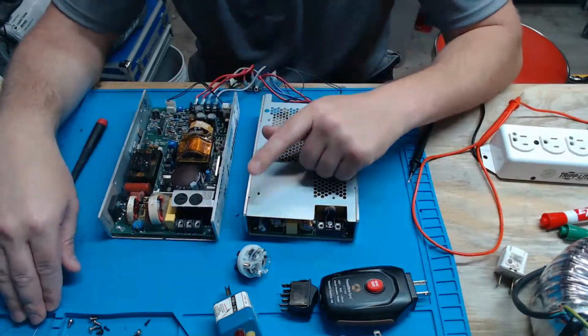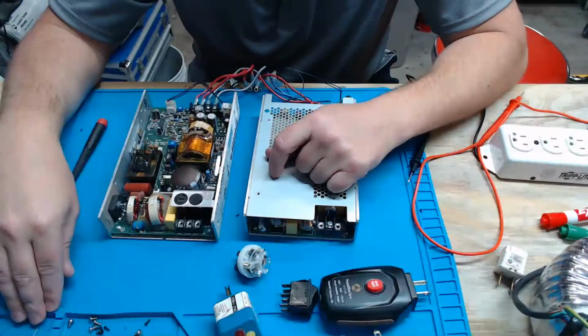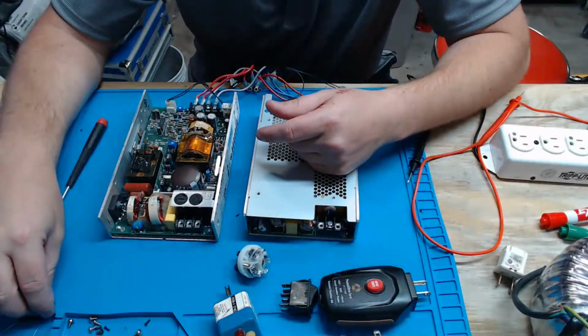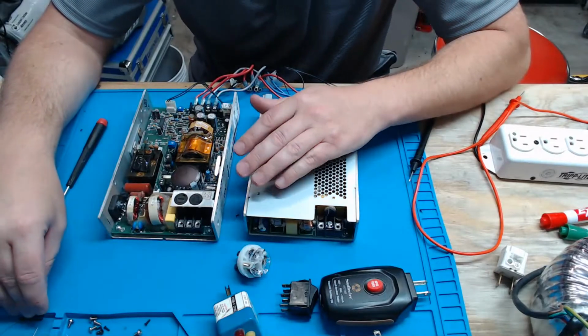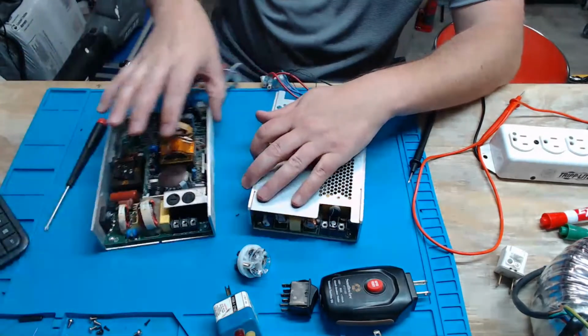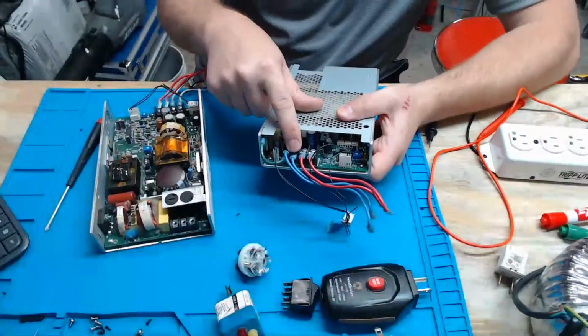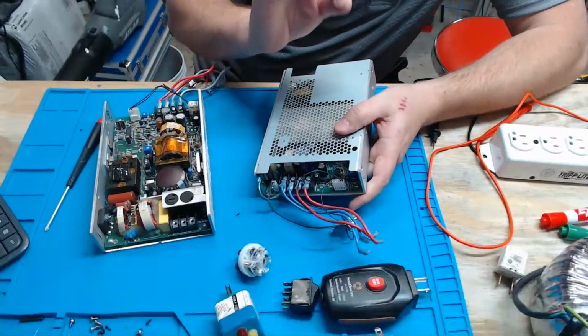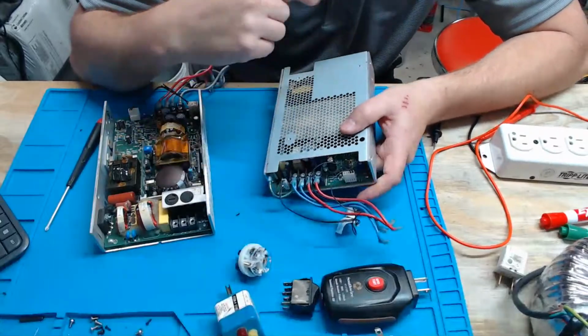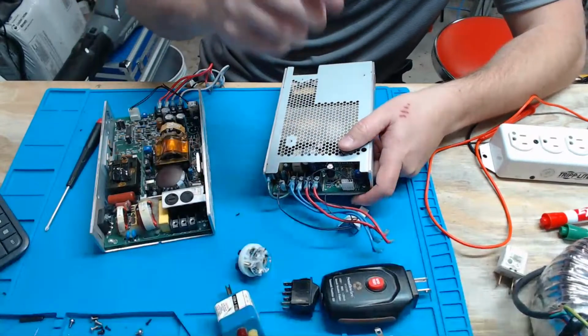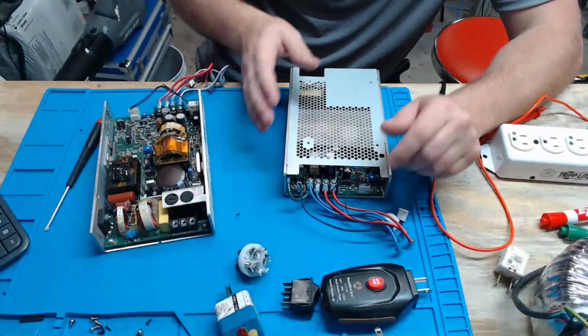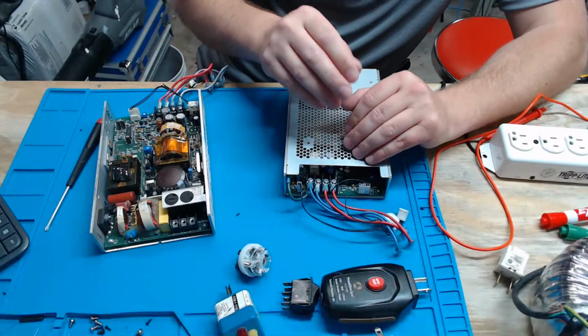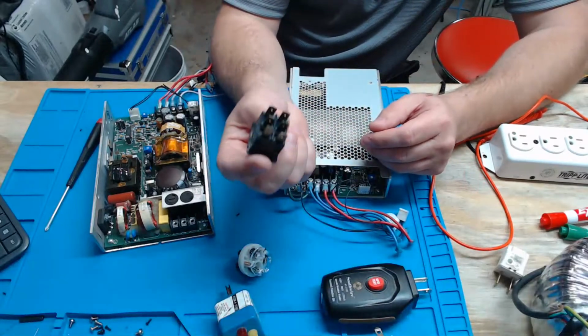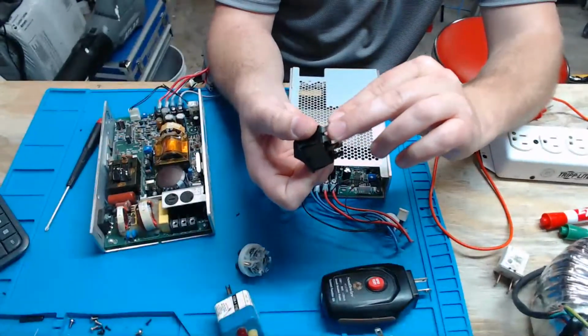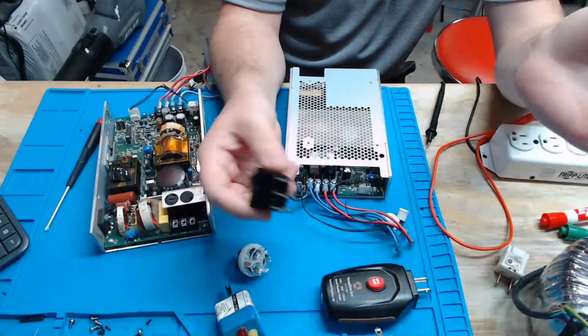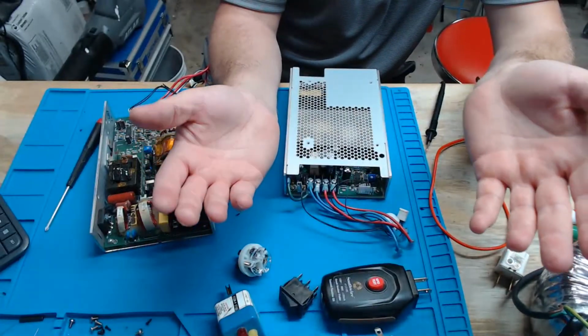And remember, guys, just because it is unplugged doesn't mean that it's safe, because most larger medical devices have battery backups, and batteries are way more dangerous than all this. But what I'm saying is, when you disconnect something, make sure you connect it exactly back to the terminal. Pay attention to your labeling. Almost every single medical device is labeled: what is neutral, what is line, what is hot. Put it back where you found it, because even something as simple as a switch, reversing your line and neutral, could be absolutely devastating. Not to you, but perhaps to your patient.